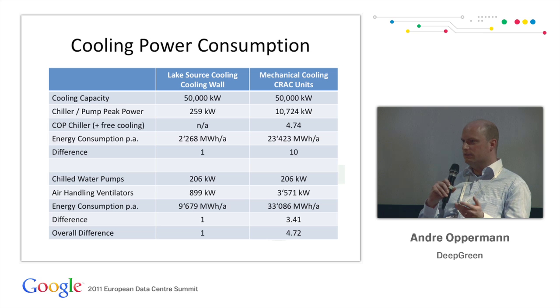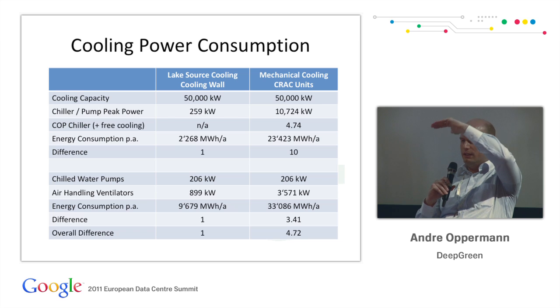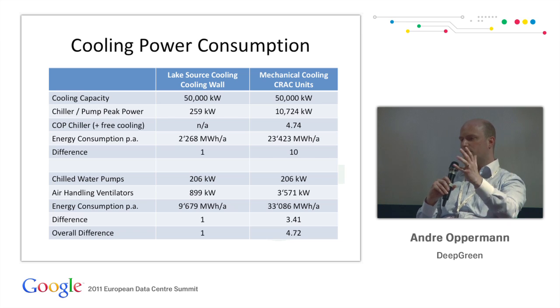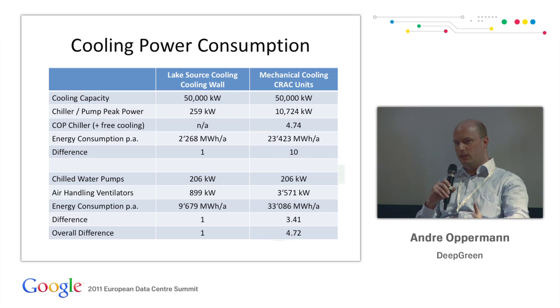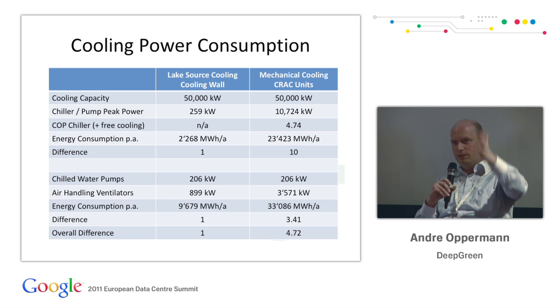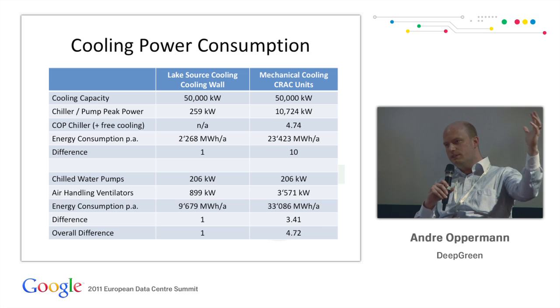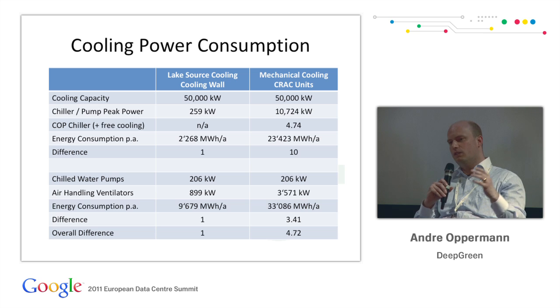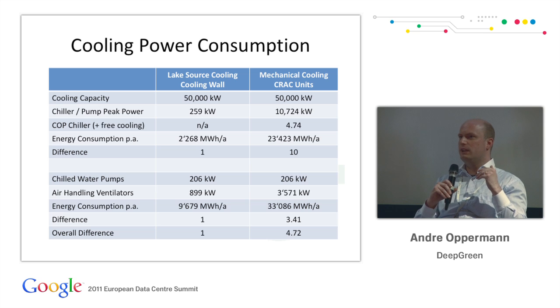So we redeveloped that into a sort of cooling wall concept, where we have a hot aisle, a plenum, and take the air through the plenum and send it back through the heat exchangers, vertically, and send the air through it again. The advantage is we have much more surface area, so a more efficient heat exchange, and less pressure drop.